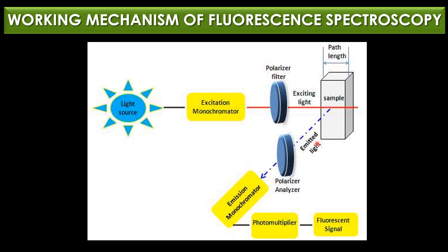After excitation, the sample emits fluorescent light typically at a longer wavelength than the excitation light. The emitted light passes through a polarizer analyzer, which filters the emitted light based on its polarization — useful for analyzing anisotropy properties. The emission monochromator then selects the wavelength of emitted light to be detected. A photomultiplier tube, a highly sensitive detector, measures and amplifies the emitted fluorescence signal, making it easier to detect lower levels of fluorescence.